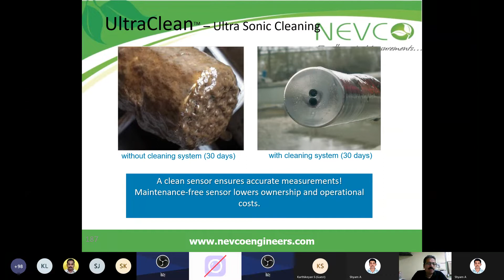Sorry. If you see, without cleaning, within 30 days this will have algae formation. As I showed in the video earlier, this is with the cleaning system. So you don't have the problem of manual cleaning or manpower going there to do the cleaning. This is auto cleaning. A clean sensor ensures accurate measurement, and maintenance-free sensors lower the operational cost of ownership. That's why this is a unique system in the world with built-in ultrasonic cleaning. Today, none of the suppliers except our WTW has this ultrasonic cleaning. We have lots of sensors running in the market today, and our technicians have a 10 to 15 minutes job.